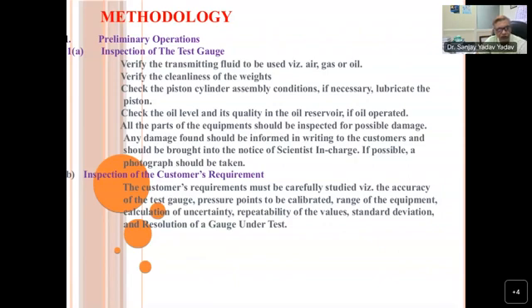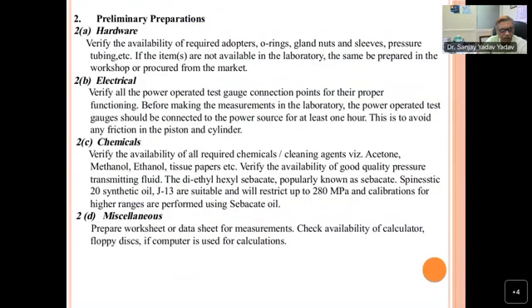Now, for the methodology inspection of this, I will explain, I think it's not necessary. Hardware, electrical, chemical, which are very important in the laboratory. Hardware, you can have adapter, O-ring, gland nut, sleeve, pressure tubing, and then electrical, you must have this test gauge connection point before half an hour. Chemicals, you must have cleaning agent, acetone, methanol, ethanol, tissue papers, di-ethyl hexyl sebacate, Spinesstic, means transmitting fluid.